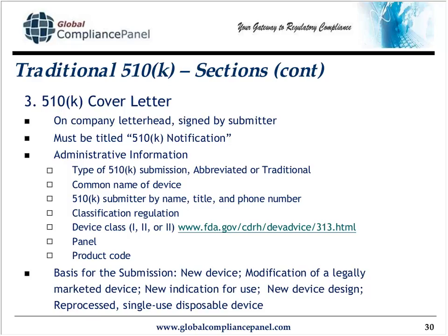The administrative section contains the type of 510K submission. Is it an abbreviated one or a traditional one? The common name of the device, the 510K submitter, and who they should call or contact, not just by name, title, and phone number, but obviously email address also. What classification regulation and device classification I'm referencing that this device falls under. The classification panel and the product code as well. And why am I submitting this document? Is it new? Am I modifying it? New indication for use?